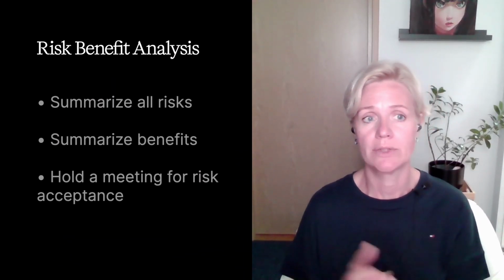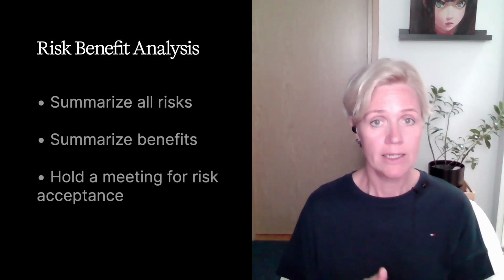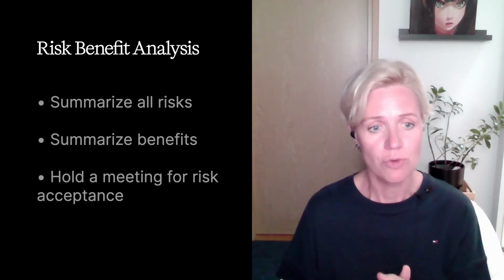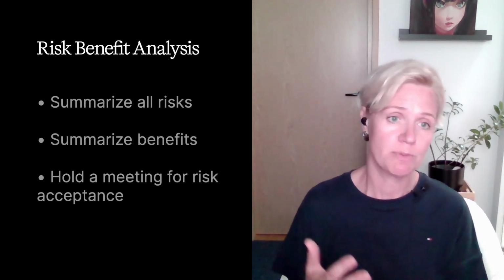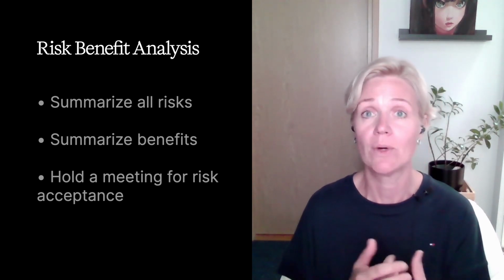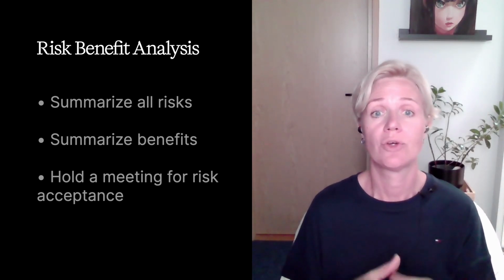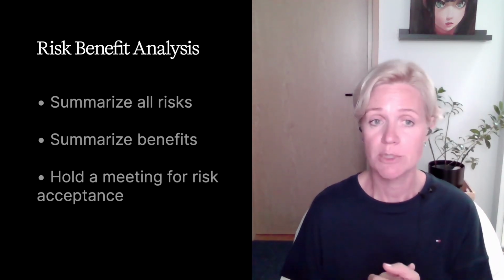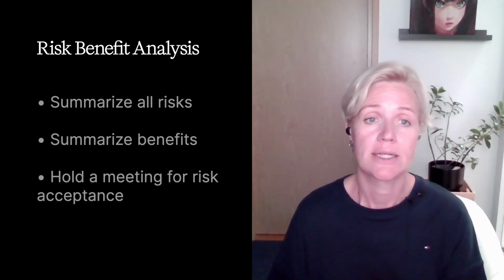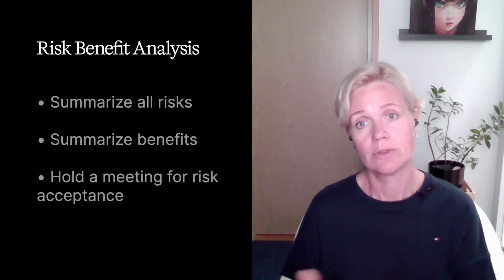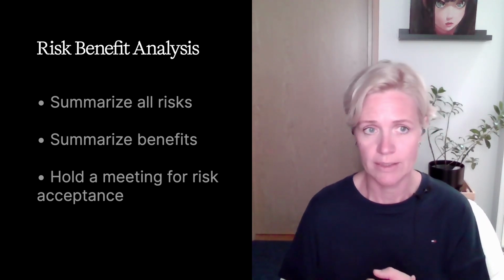First, you will have to summarize all the risks, including residual anomalies or software warnings or contraindications and so on. Then you will have to summarize all proven benefits of the use of the device. And finally, you have a meeting with a project team, management team. You will also include regulatory and quality people, and if possible, also an external expert of the device. And at that meeting, you agree that the risks have been mitigated as far as possible, and additional risk controls do not significantly reduce anymore the risk, and agree that each residual risk and the overall medical device residual risk is acceptable because the benefits of using the device outweigh the residual risk.